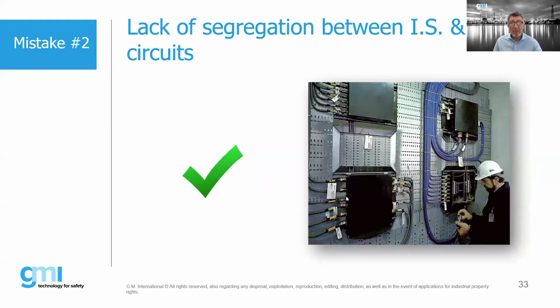There was some question about power cable and IS cable. Obviously, they cannot cross each other. They need to be kept separate, as we just discussed. Yes, to an extent, although we can have power cables with armor that can be used as a means of separation, segregation. In any of those situations, the standards are basically written very similar, but there may be clients around the world that will say, I do not allow that. So realize what we're telling you here are the generalities, the commonalities with a lot of standards, but always make sure you find out what is the relevant standard, what is the requirement for your country, what are the specific client requirements, or what are the requirements you put in to make sure that you're in compliance.